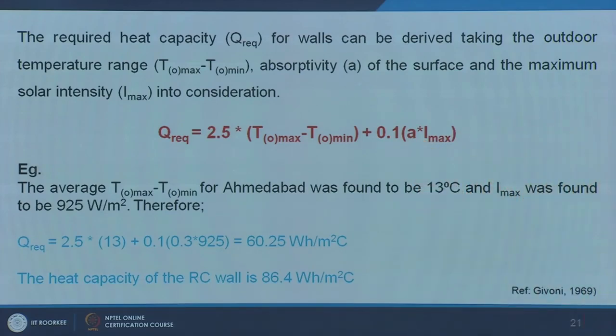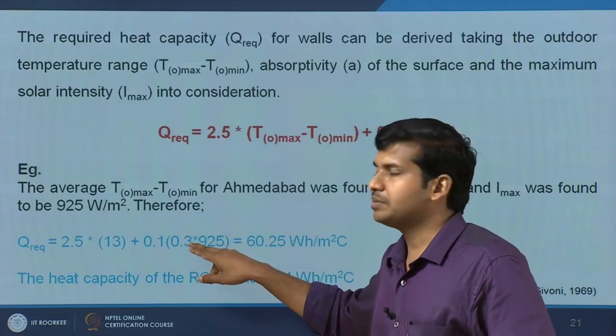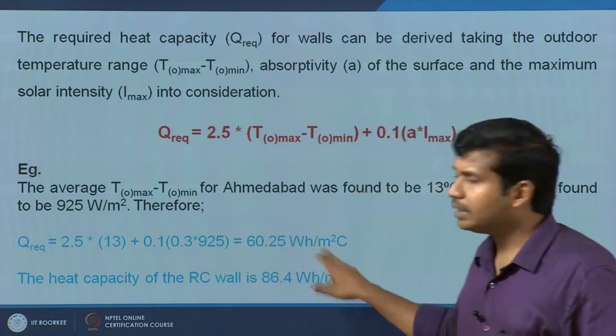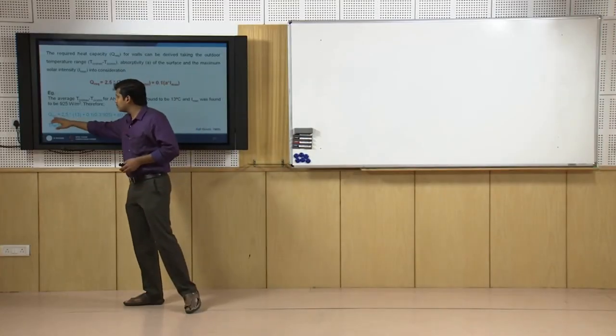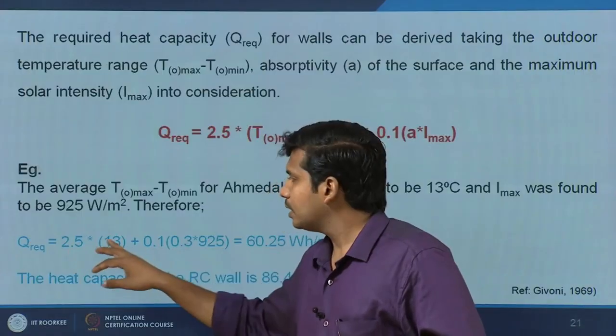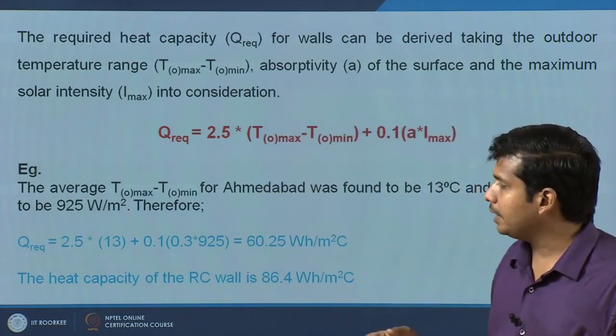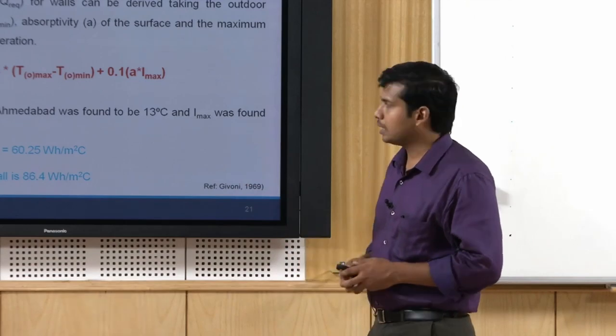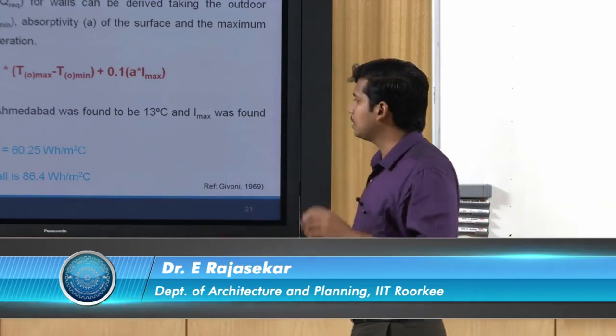If instead of a white-painted surface with 0.3 absorption coefficient, we substitute a matte black surface with 0.85 or 0.9 absorption, Q required goes up considerably — a dark surface requires more thermal capacity than a light surface. As diurnal delta T increases, Q required goes up; as solar intensity increases, required heat capacity also goes up. This equation is not precisely validated for the Indian context but gives a fair idea of where thermal capacity is needed and to what proportion.